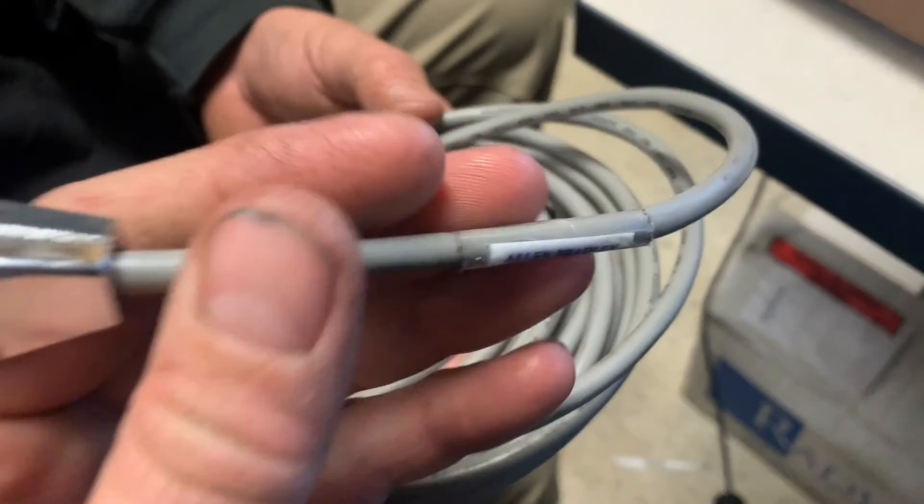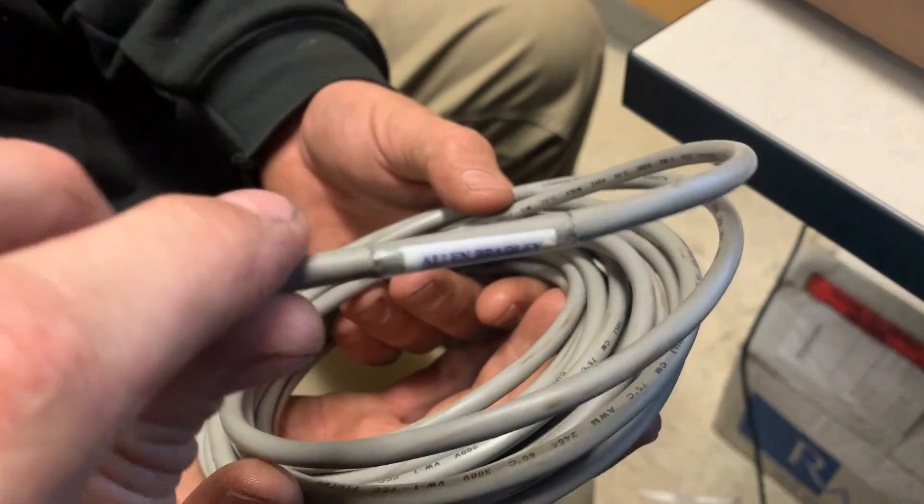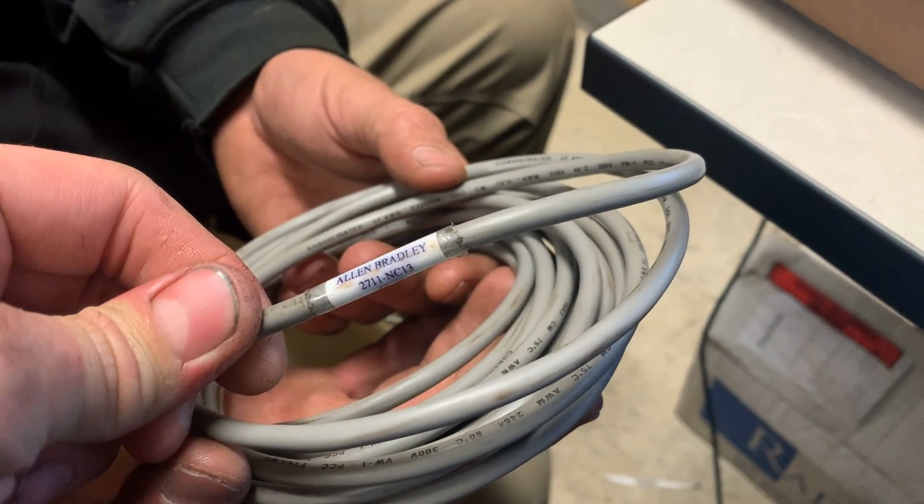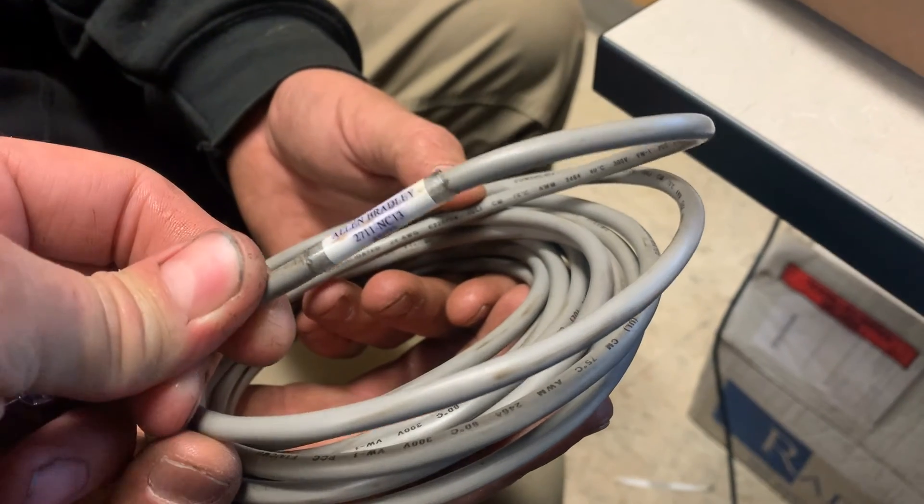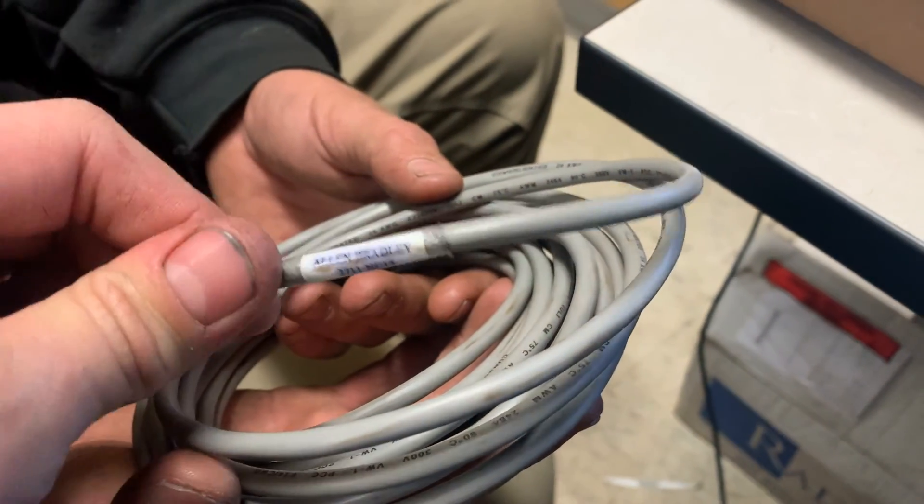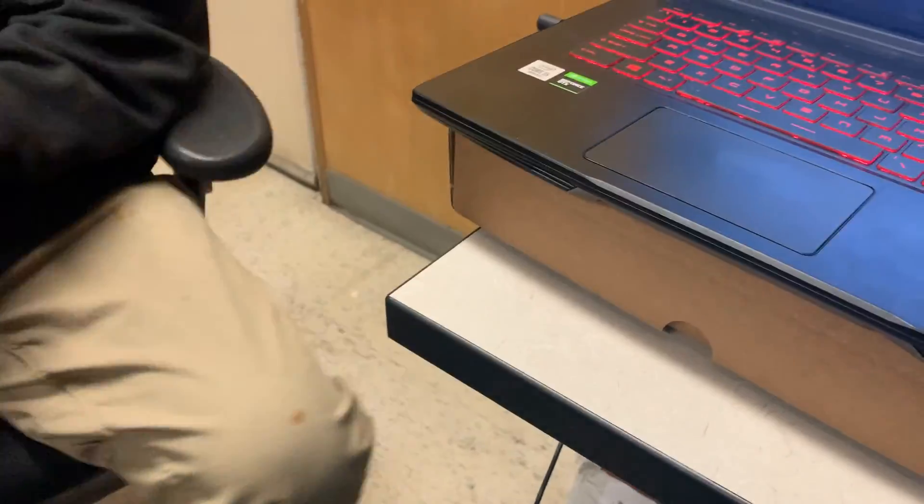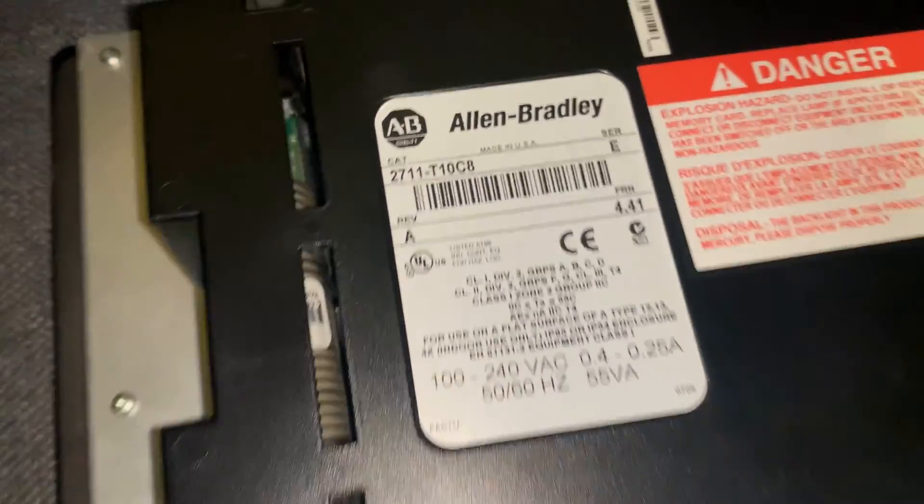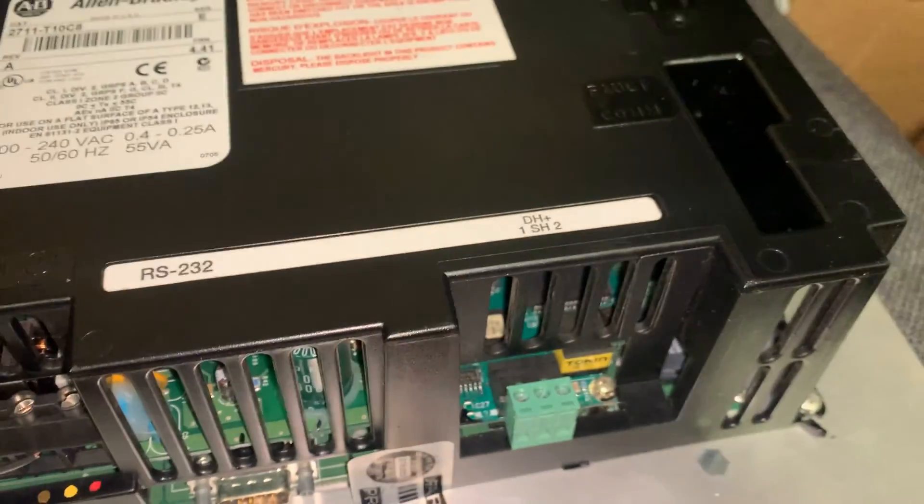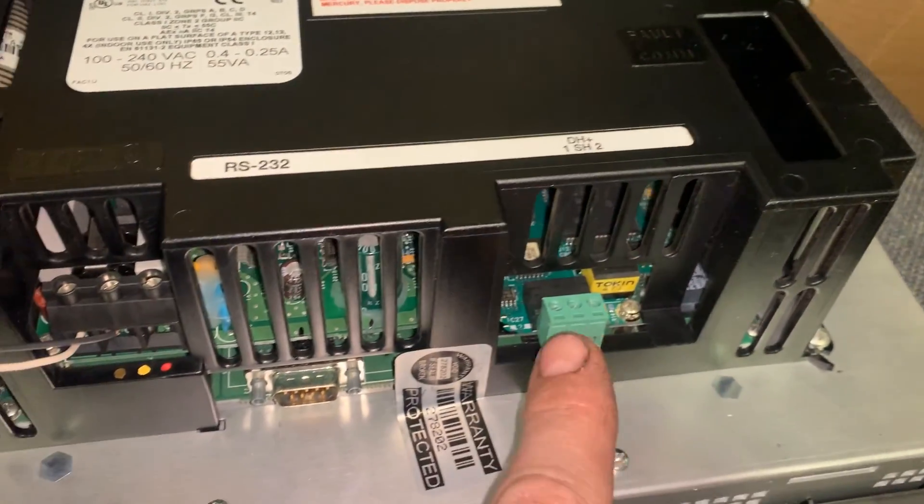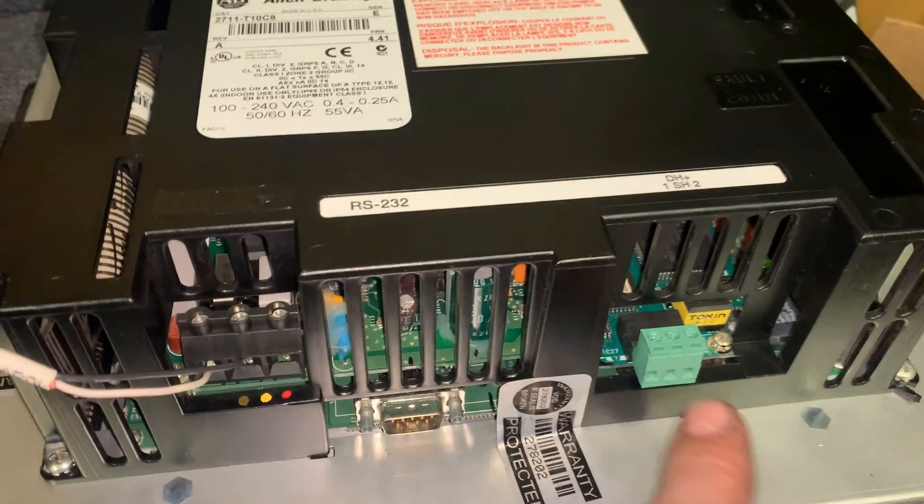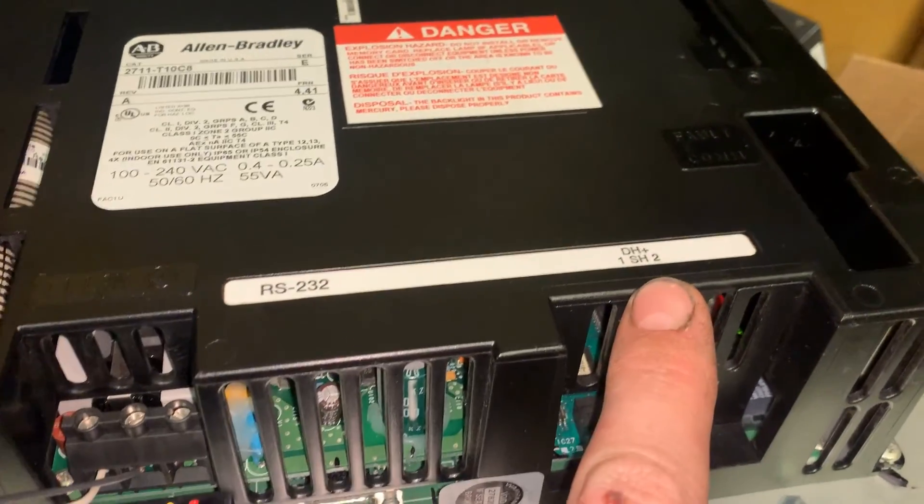This one is specifically for our application, this is a 2711-NC13. The 13 or the 14 will work, they're just different length cables. This is specifically for the 2711-T10-C8 or any of the DH Plus communication module models. This one's primary communication is DH Plus.